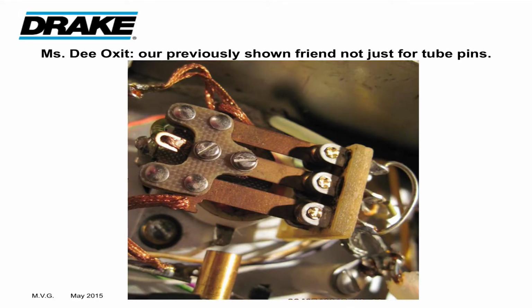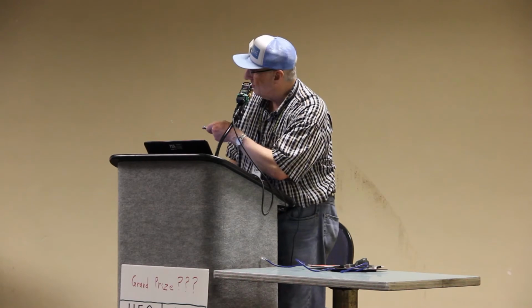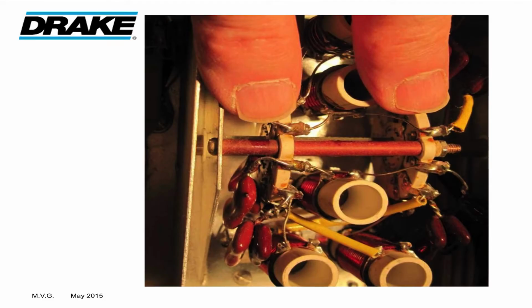With regard to the relay, typically what I do is I take each one of these contacts on this side as well as on the bottom side, and I run a clear piece of unused paper, white paper, through there and see if you get any oxidation or dirt. If there's very much there, you might want to try the deoxid, or you may even have to burnish the connector. Here you've got the two input wafers on the L4B. Inspect those to see if you got any dust or corrosion of any sort there, and if there is, then you can use the deoxid.